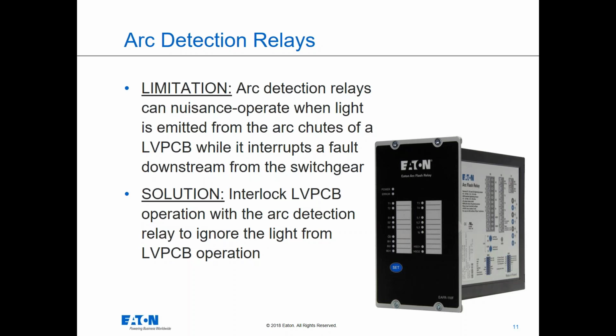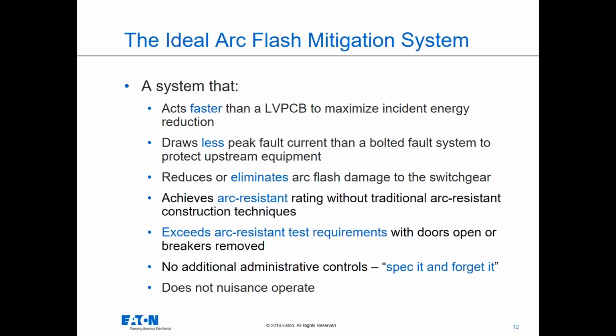So when you are modeling the system for clearing time, you still have to rely on the actual circuit breaker to make sure that your clearing time is accurate. The arc detection system, including Eaton's, is not by itself able to claim the actual reaction time to quench or to stop the arc.